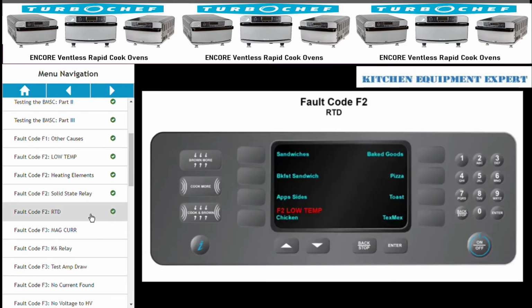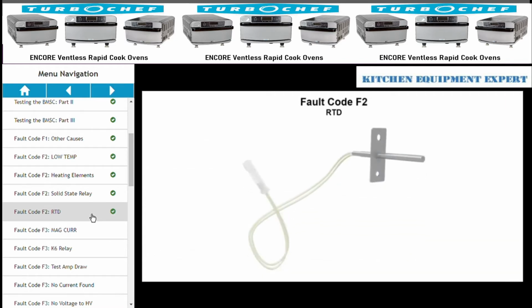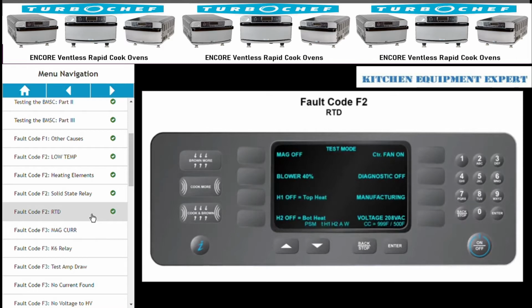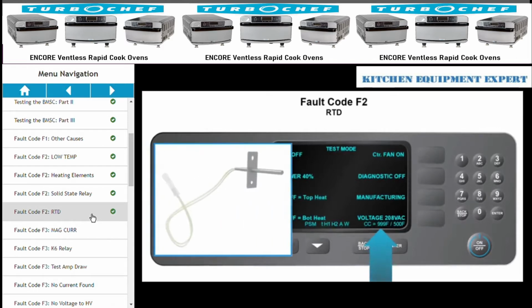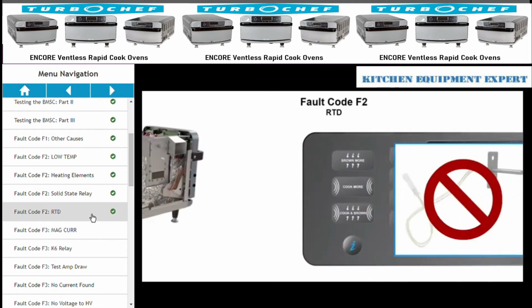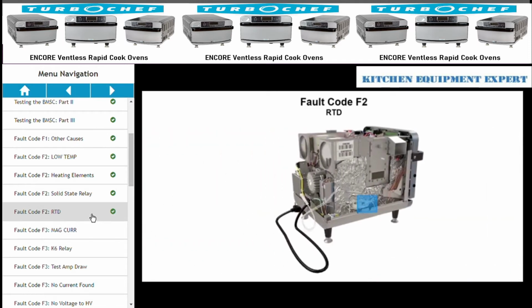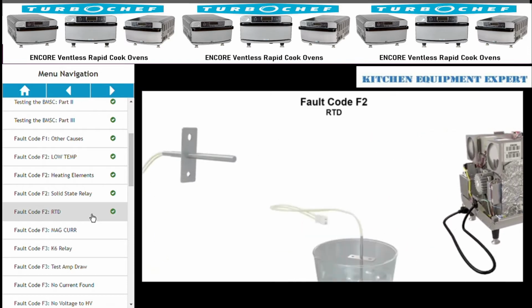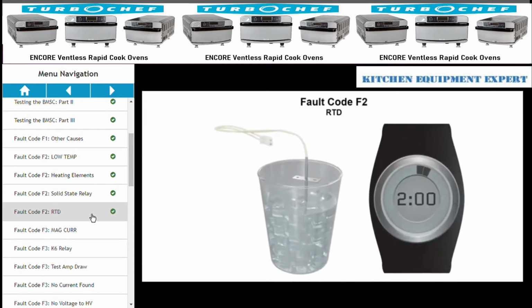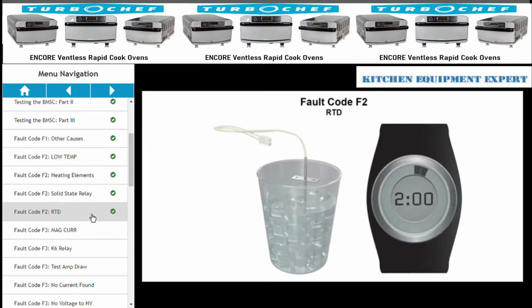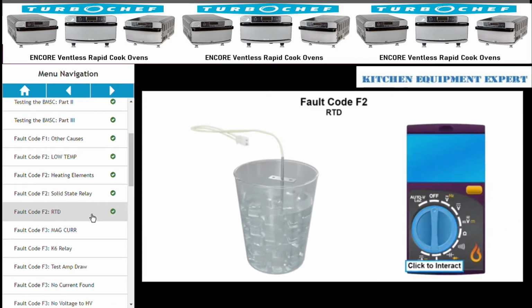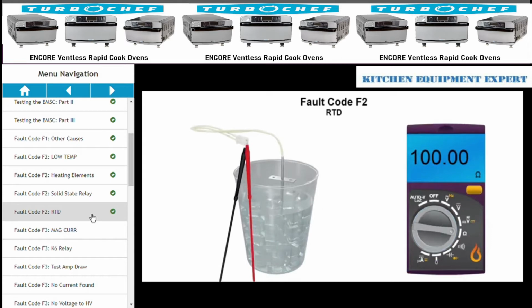Another possible cause of an F2 is a faulty RTD. Since this is the device that's sensing the temperature in the oven, if it's malfunctioning it will provide bad feedback to the controller. If you see a temperature reading on the display of 999 degrees, the RTD is open and must be replaced. To test the RTD, remove it from the oven. Place the sensor bulb in an ice water bath for 2 minutes. With your meter set to the ohm scale, test the RTD. You should see a resistance reading of about 100 ohms.